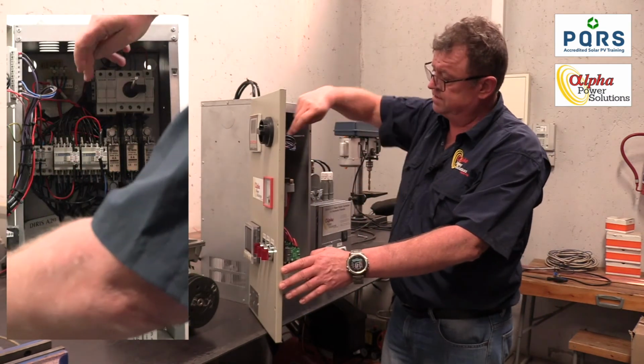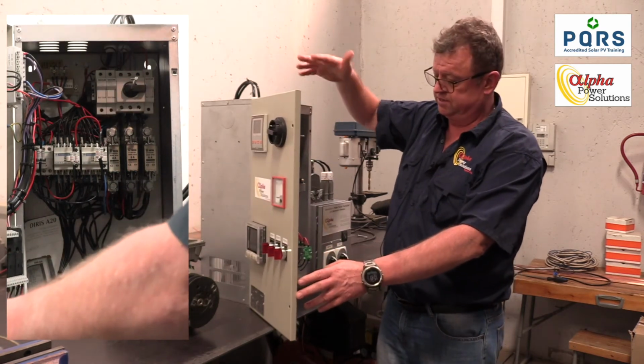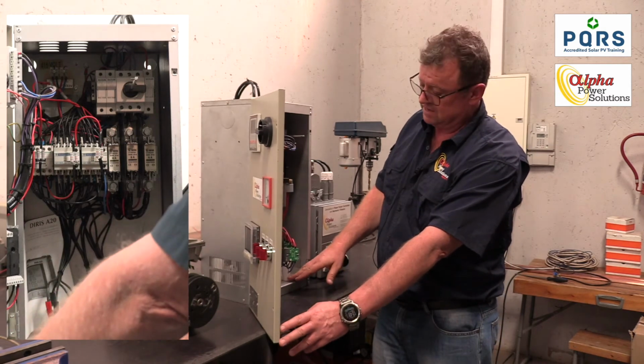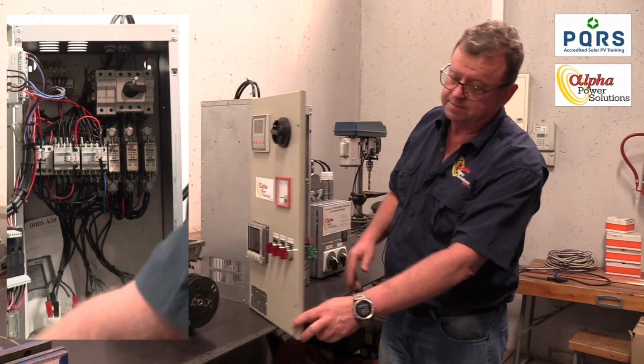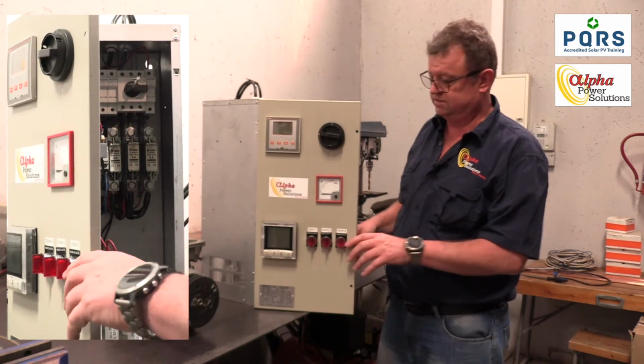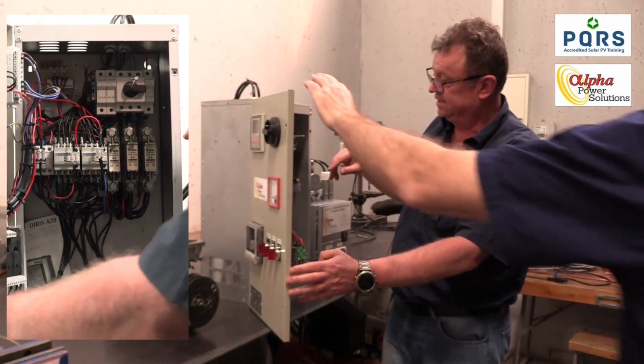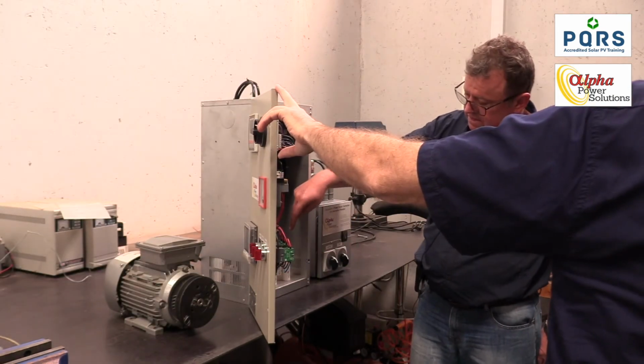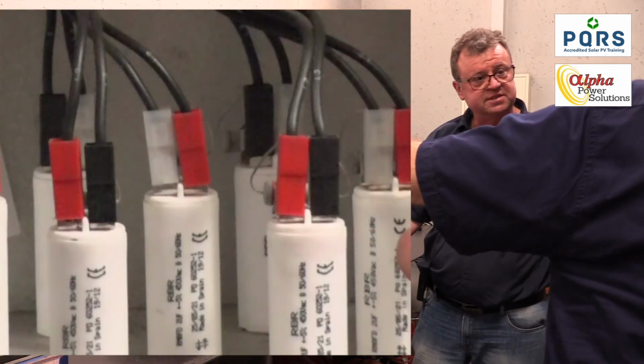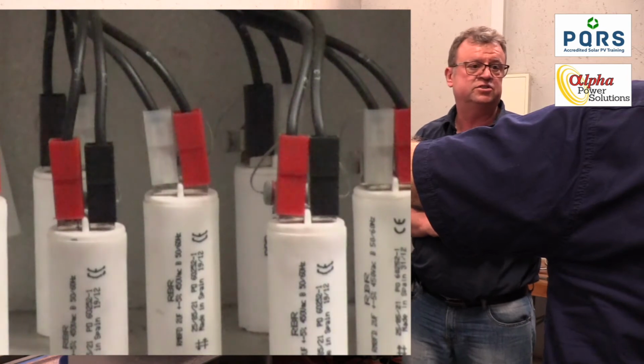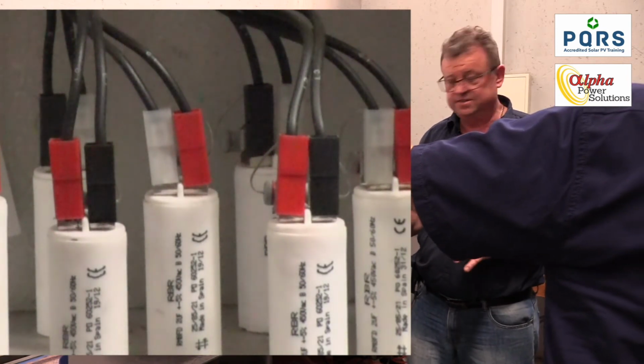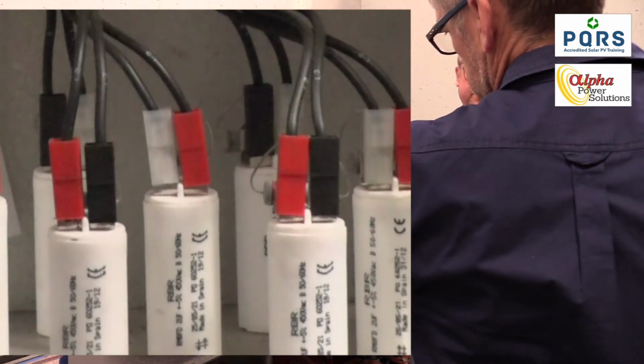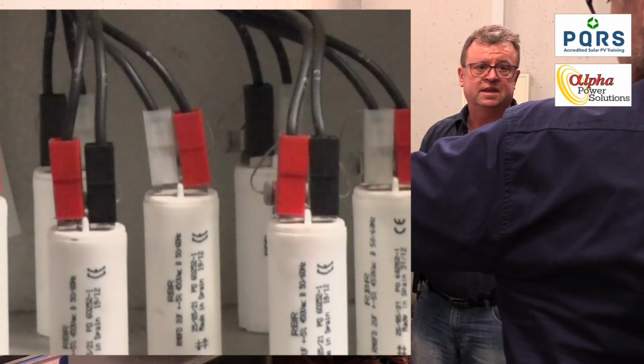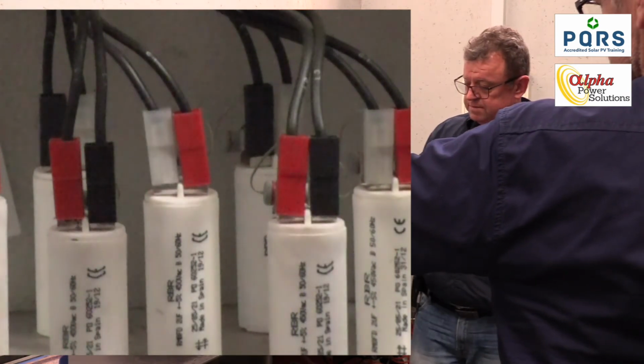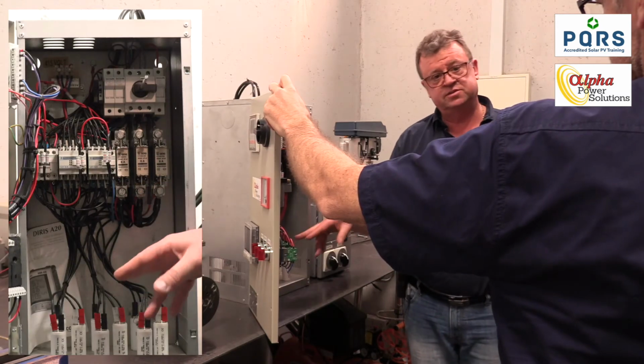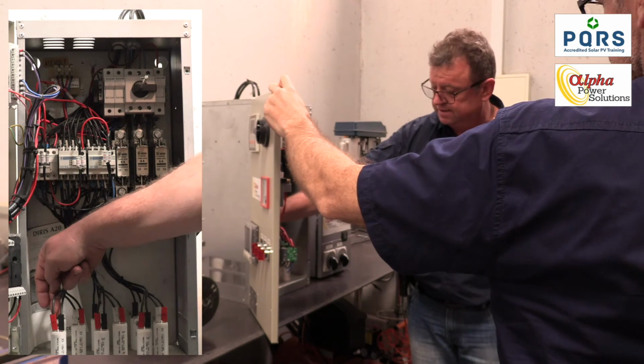These are the contactors. They're obviously way overrated for this application, because this is the size of the capacitors. You only need these capacitors to fully correct, but we had to do some sort of simulation. So these are the capacitors, and behind each capacitor you will see there is a discharge resistor. Capacitors need to discharge, otherwise they become extremely unsafe, and big capacitors store enough energy to kill you if you touch them when they're not fully discharged. So by law you always have to put the discharge resistors as close as possible to the electrical connection. So they're sitting right behind here.